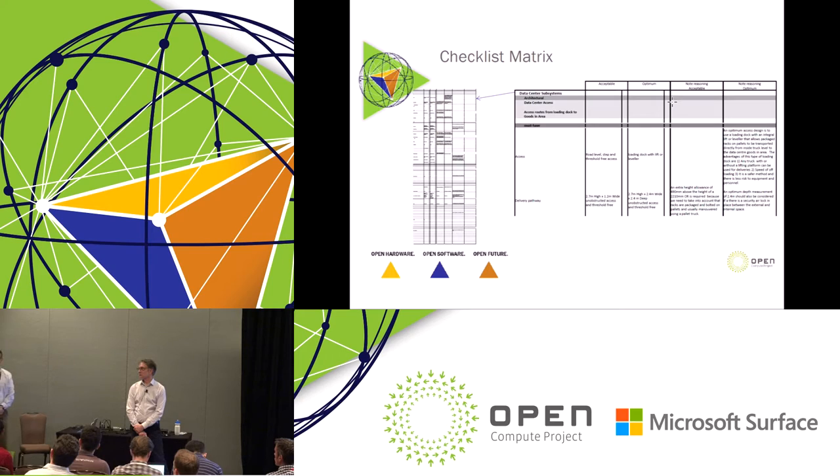There's going to be a separate doc that we'll eventually get out that depicts what those colors are and how the cables should be labeled. All we're really saying on these cables is get away from that EIA colored standard of the jacket being colored, saying aqua and teal and orange and whatever those colors are from all those different things. Because who knows what multimode color they're going to come up with next for OM5 or OM18, whatever they come up with next. Keep those on the connector heads, but then the jacket color itself come up with a defined color scheme. We've come up with that with red, blue, black and some other colors. We can show the schema later, but really what it's about is operationally it makes it easier for the guys that are in the data center to get there and figure it out and get the stuff fixed faster.